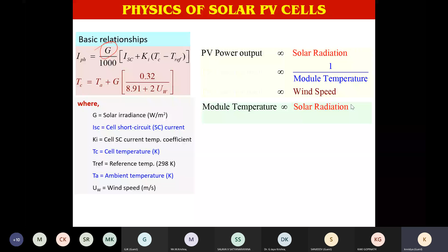Now there is another relationship, that is with wind speed. Temperature and wind speed have a direct correlation. When wind speed increases, temperature comes down, and when temperature comes down, solar PV output will increase because the losses come down. It is not that the radiation level is changing. For the same solar radiation striking a PV cell at a particular ambient temperature, output will be higher if wind speed is more, or lower if wind speed is low. You can feel this effect especially during peak summer, the June-July period.